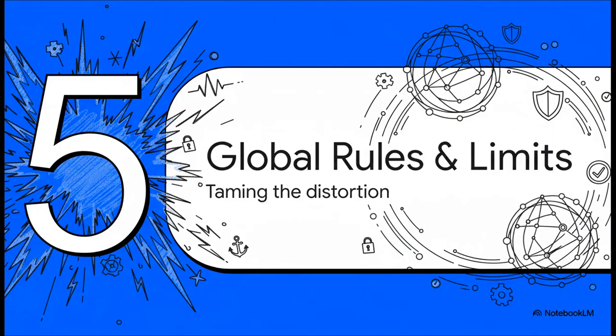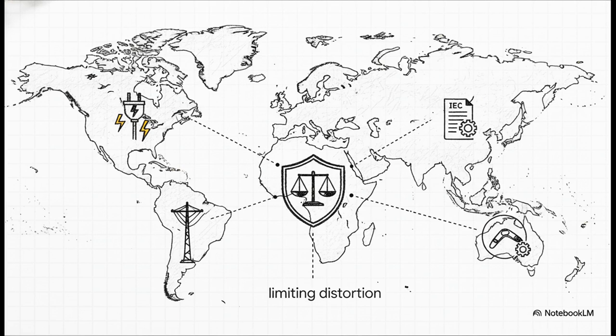This is clearly a huge global problem, and because it's so serious, a whole framework of rules and standards has been developed around the world to keep this electrical pollution under control. In North America, the big one is IEEE 519. Internationally, you've got the IEC 61000 series, which serves as a foundation for countries everywhere. You see it adopted as AS/NZS 61000 in Australia and New Zealand, or as the ENA G5 recommendation in the UK. The physics is the same everywhere, but each standard is tweaked for the local grid. The goal is always the same: limit harmonic distortion.